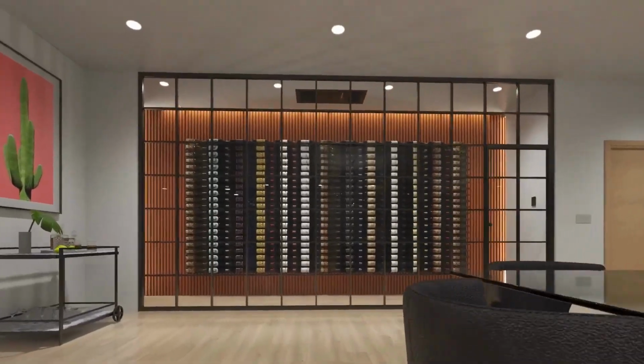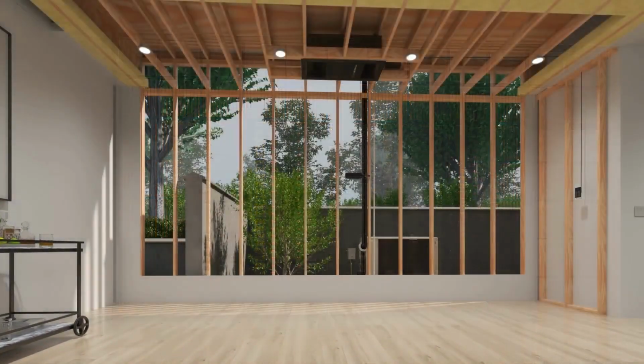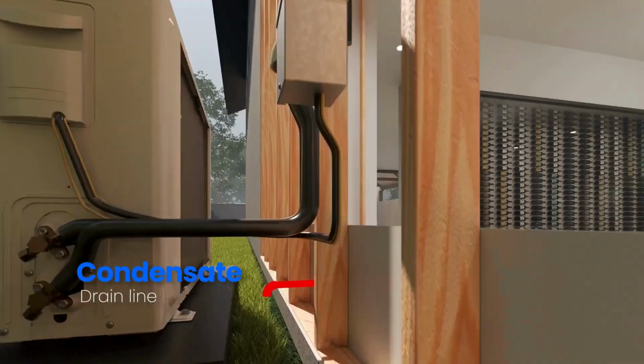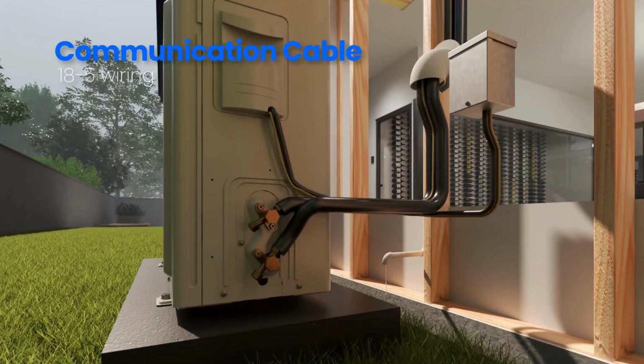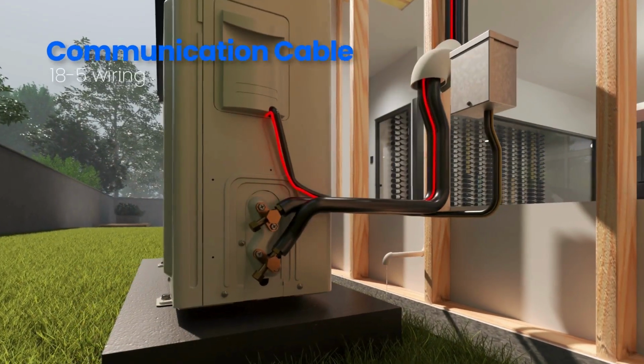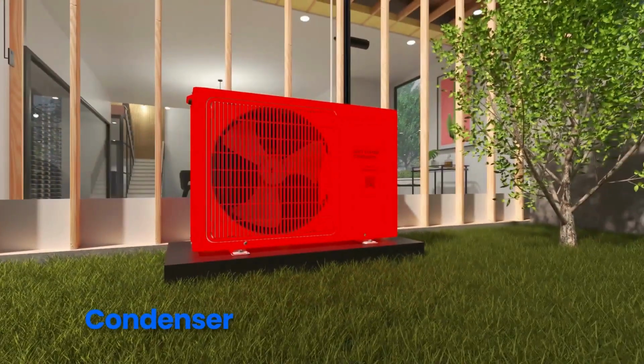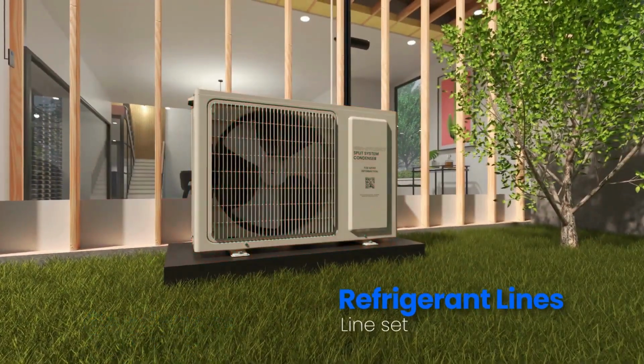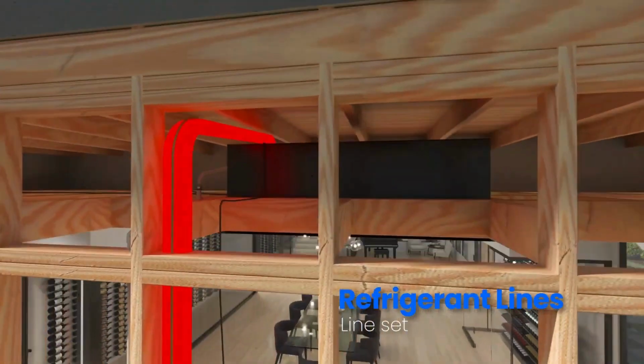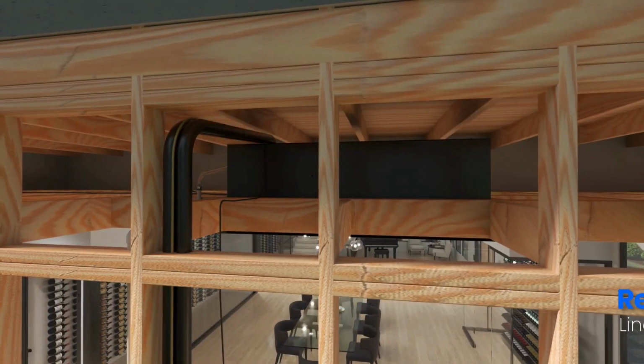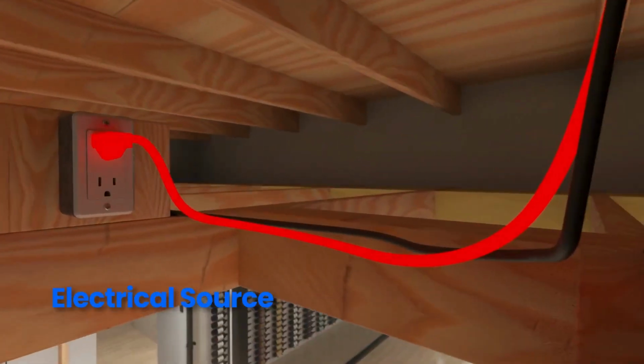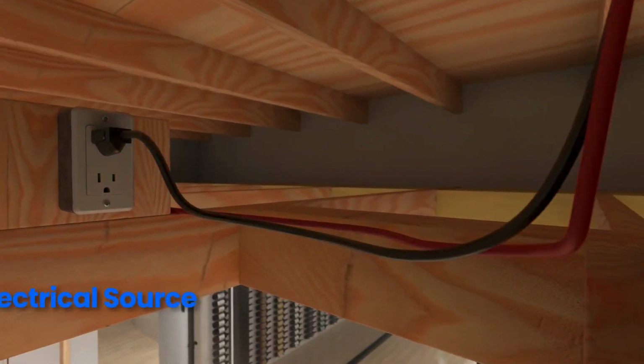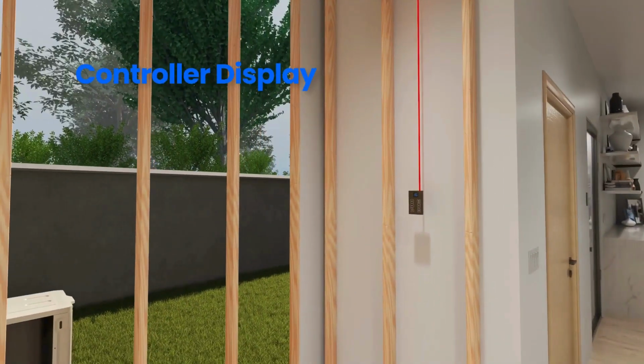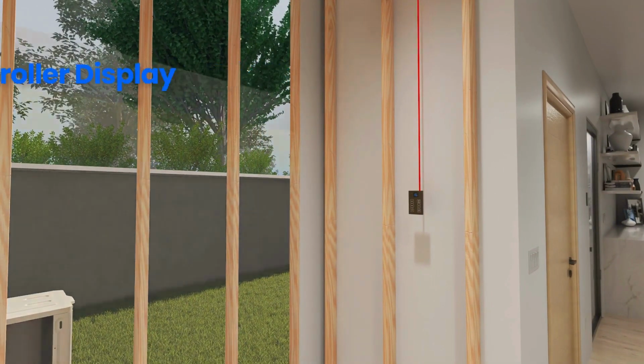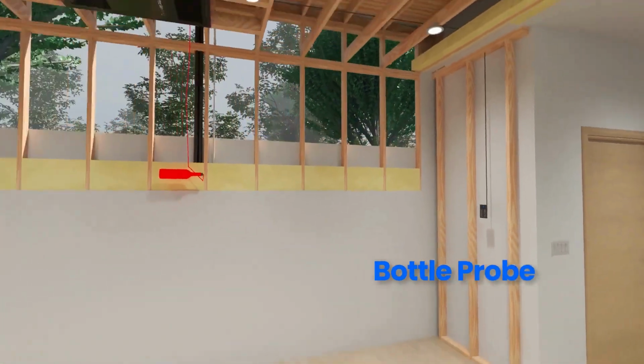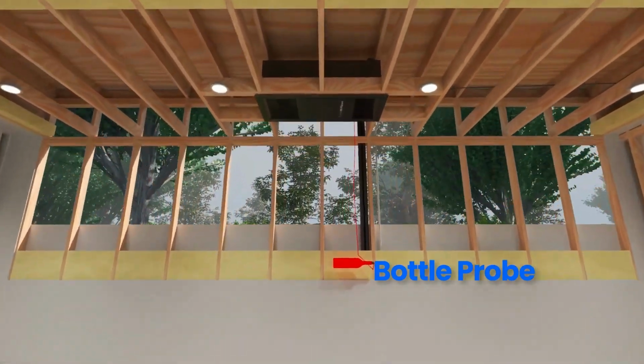There are a few components that need to be considered when installing a ceiling mount unit: a condensate drain line, an 18-5 communication cable, the condenser, refrigerant lines or line set, an electrical source, the controller display, and the bottle probe for measuring liquid temperature in the cellar.